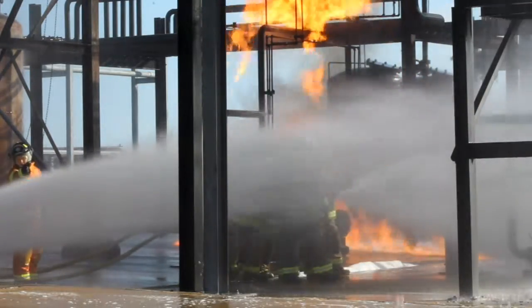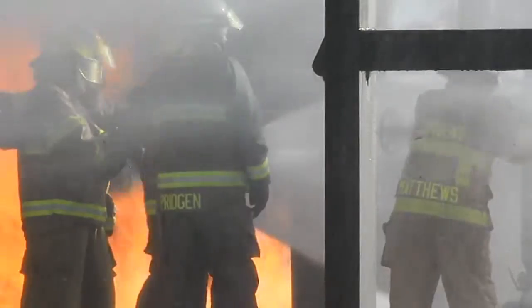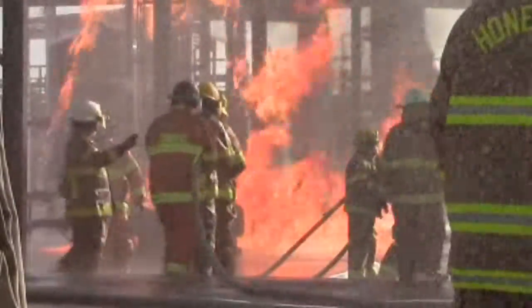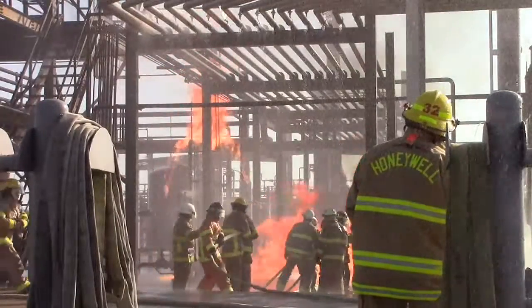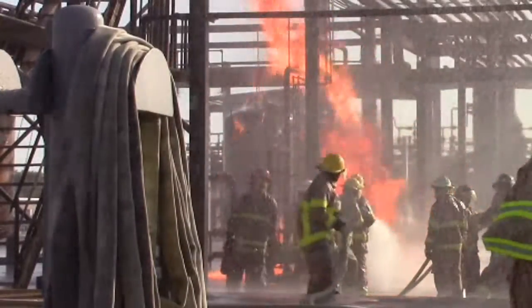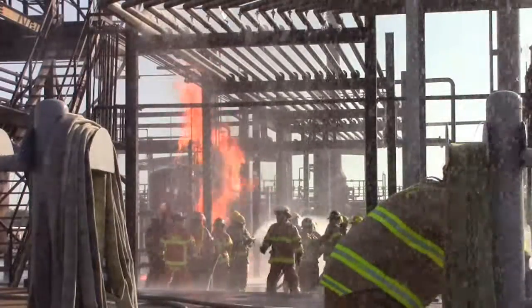That's on fire. Once we get control of the aerial cooler and the pumps, as soon as we can release the blitz, the blitz is going to reset up and let them capture that flange back here. Hose lines one and two, all you have to do is mop up anything it's not capturing. We've got to go in and make two blocks — one upstream, one downstream. If the fire's in the middle, we'll take all that fire out the back. If we need to, we'll come in with a little dry chem for mop-up, then go in and make the two isolations.